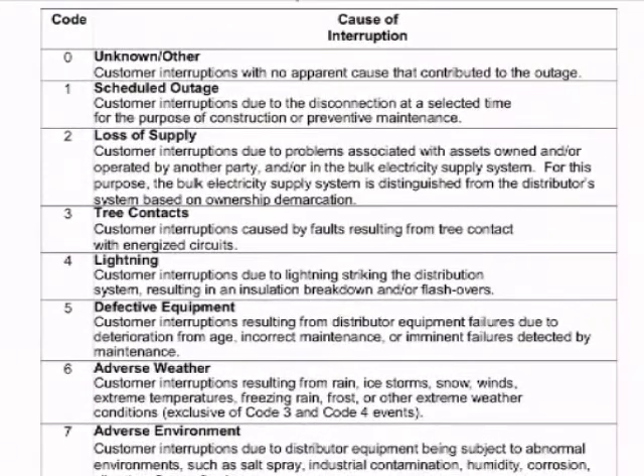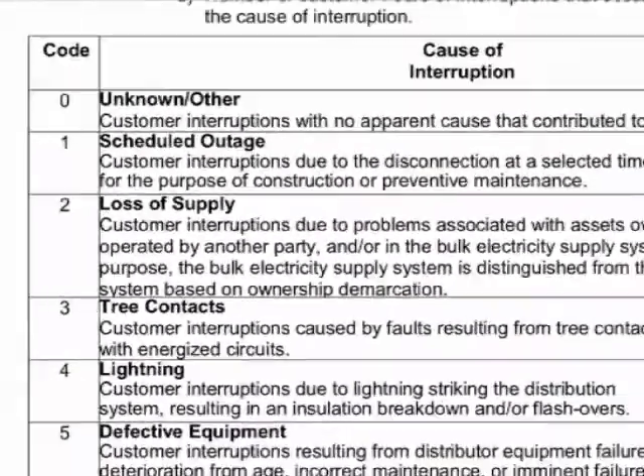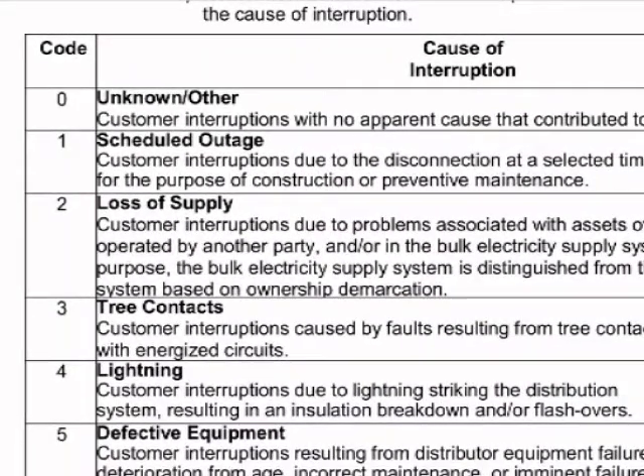First cause code we have is for an unknown outage. So this is where you have an outage, you investigate, and there's no evidence of damage. You put a new fuse in, you close the breaker back in, everything's all right, and you're never able to trace it down to a root cause. A second type of outage that you can see occurring is a scheduled outage. So if you're doing conversion work, if you have to replace a customer serving transformer, in order to do that replacement, you're going to have to take those customers out of power. So you could have a scheduled outage.